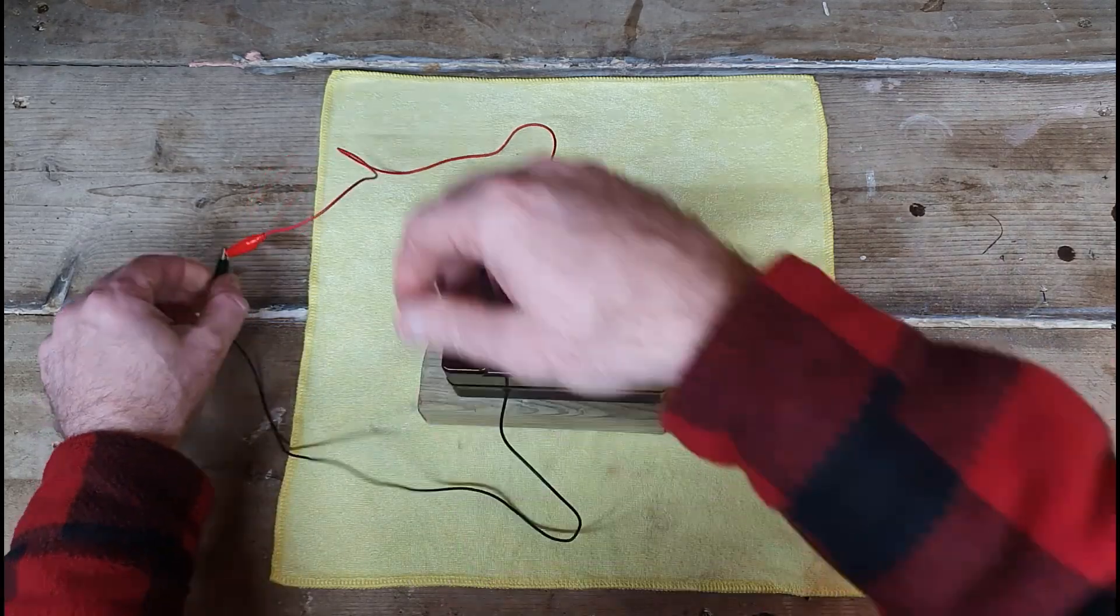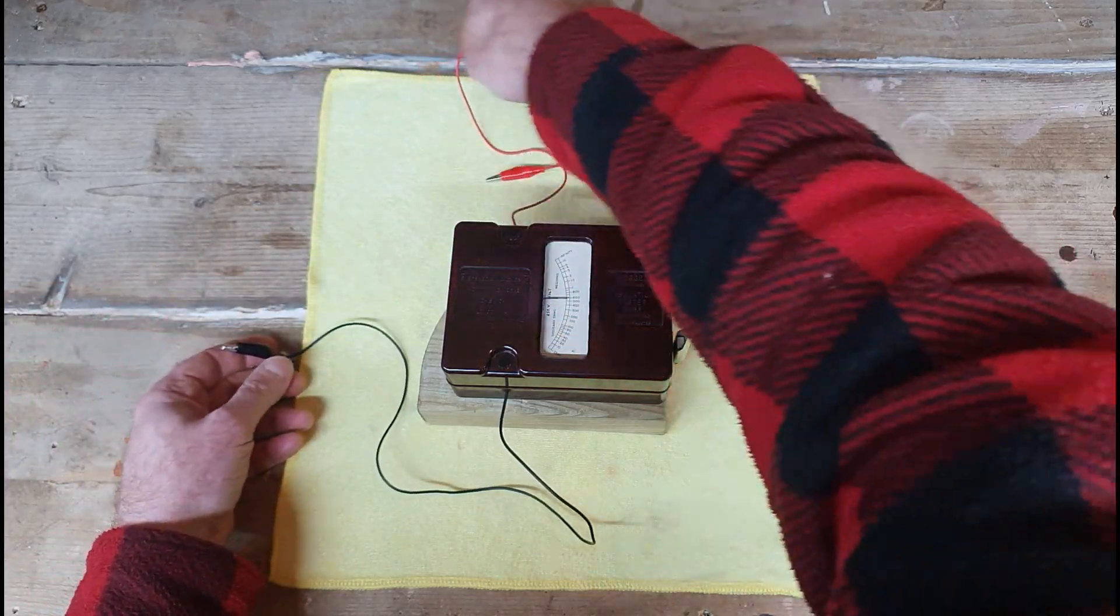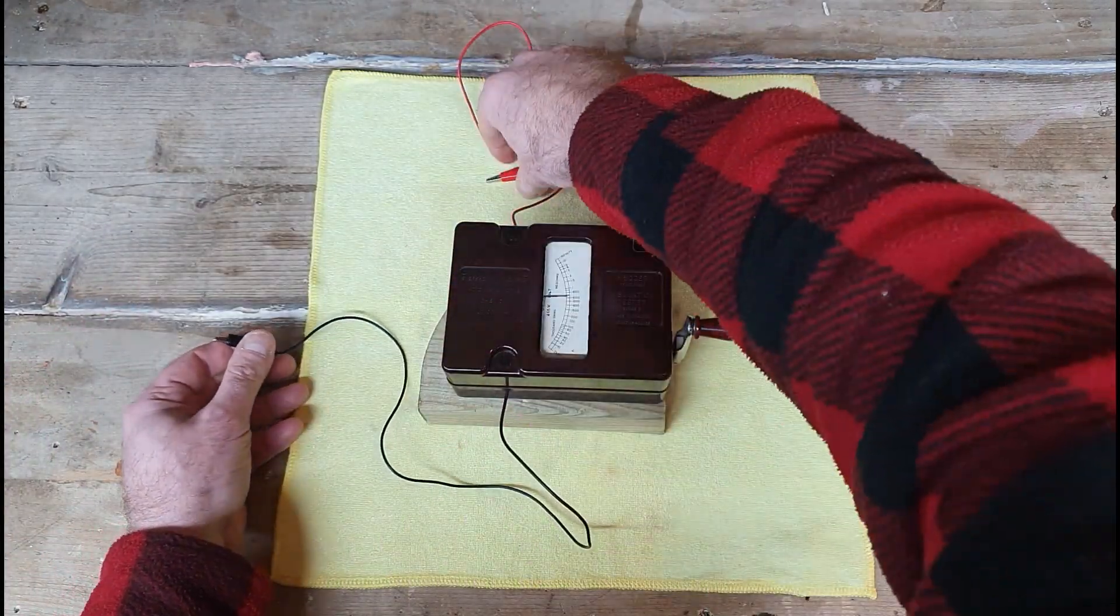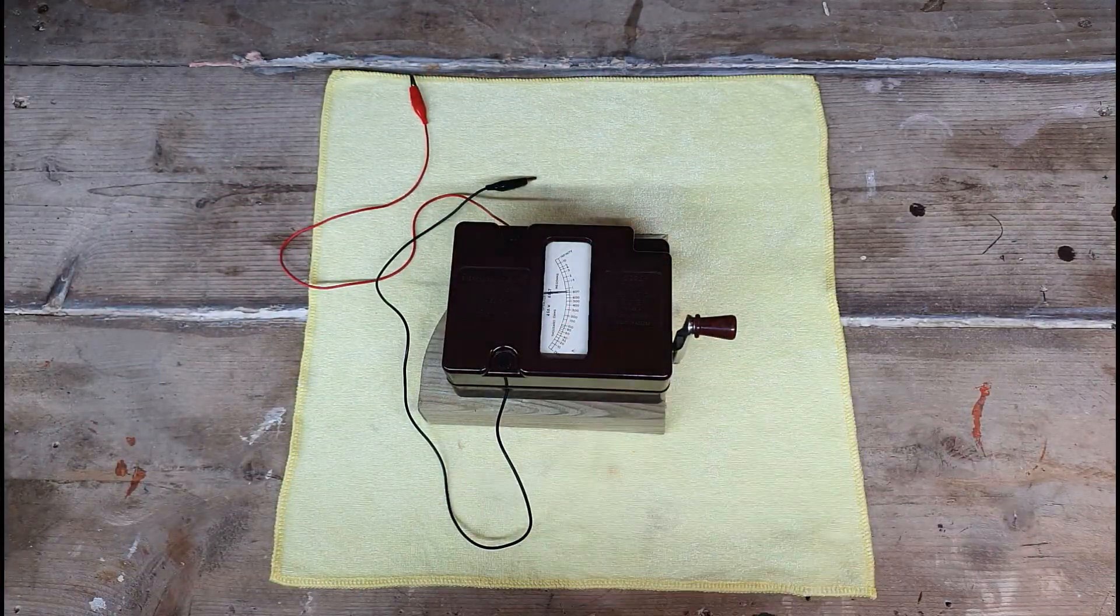Wow, yep. Obviously insulation has been compromised because it's basically a dead short out of here all the way around back to there, and it's showing on the analog needle.